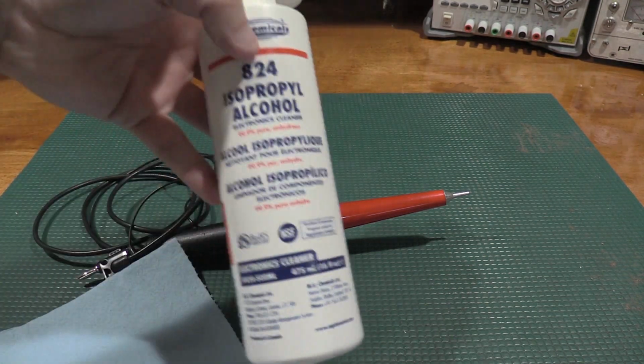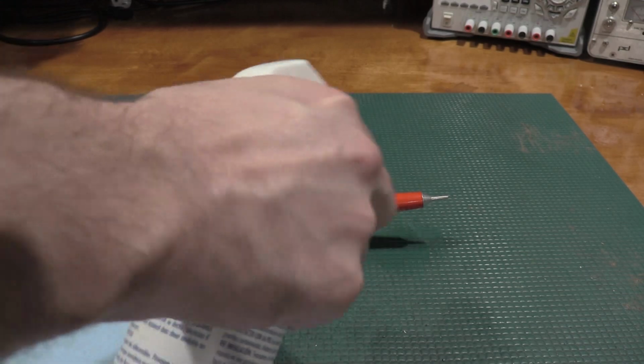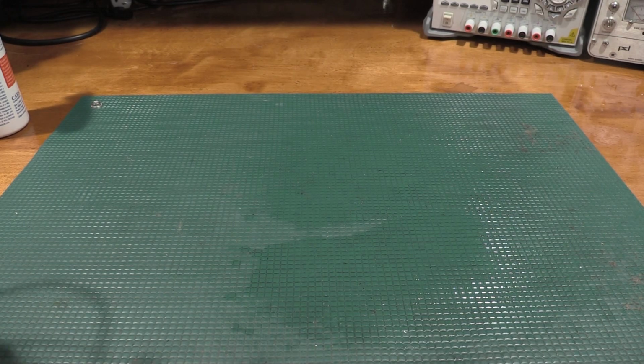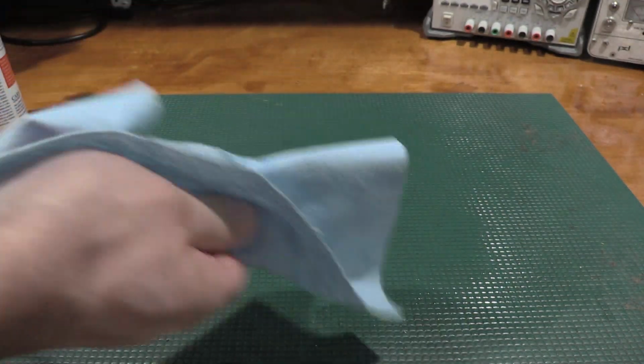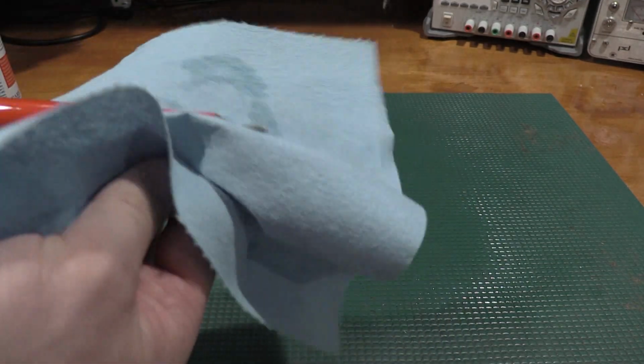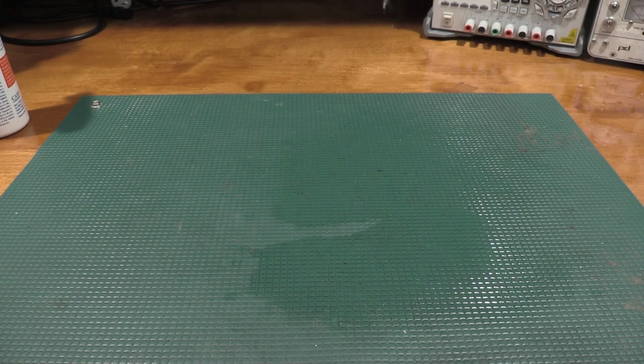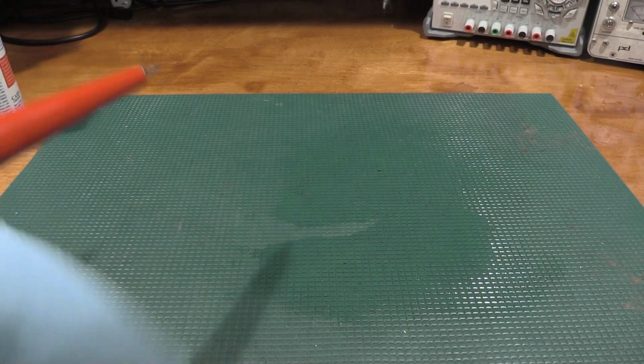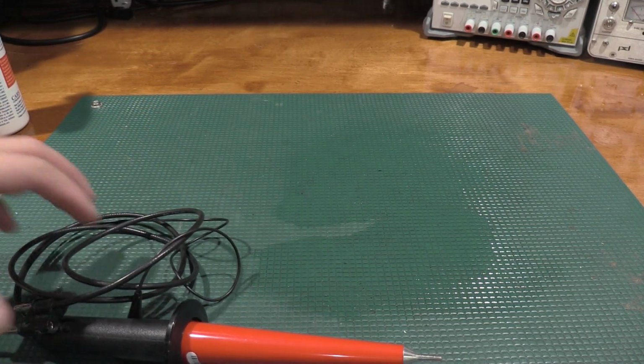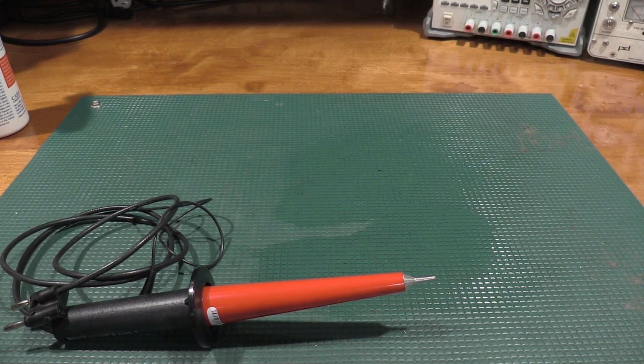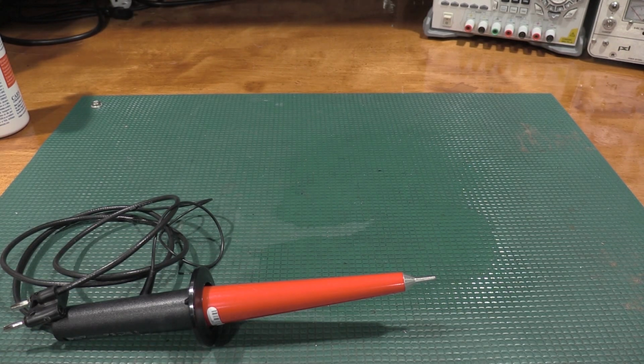Okay, to clean the probe, we just use some 99% isopropyl alcohol to cut the grease. And just wipe this down. Make sure to get all the grease and oils and stuff off of anything that's red, typically. The red parts are the ones that are contaminant sensitive, but we'll wipe down the whole thing just in case. Now I'll let that sit. I won't use it right away because I want all that alcohol to flash off, because obviously I don't want something to arc up through the alcohol, and then not only am I getting shocked, but I'm also on fire. So that would be a bad day. So definitely give it a chance to flash off.